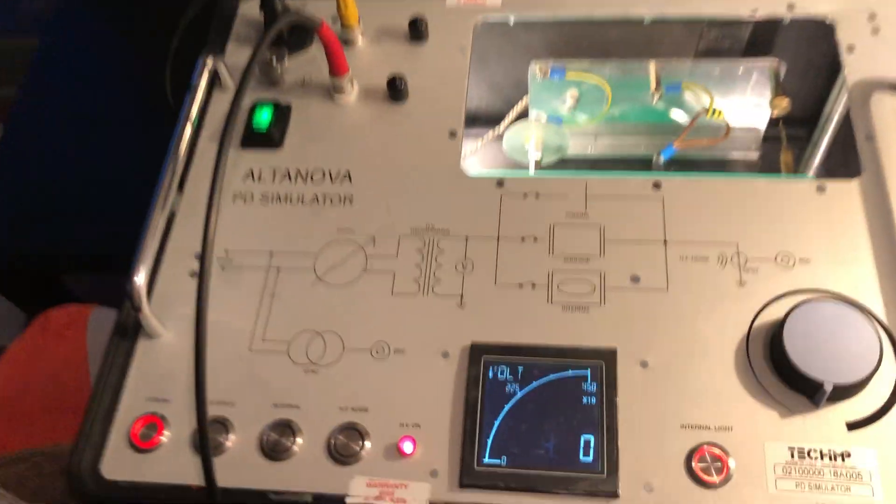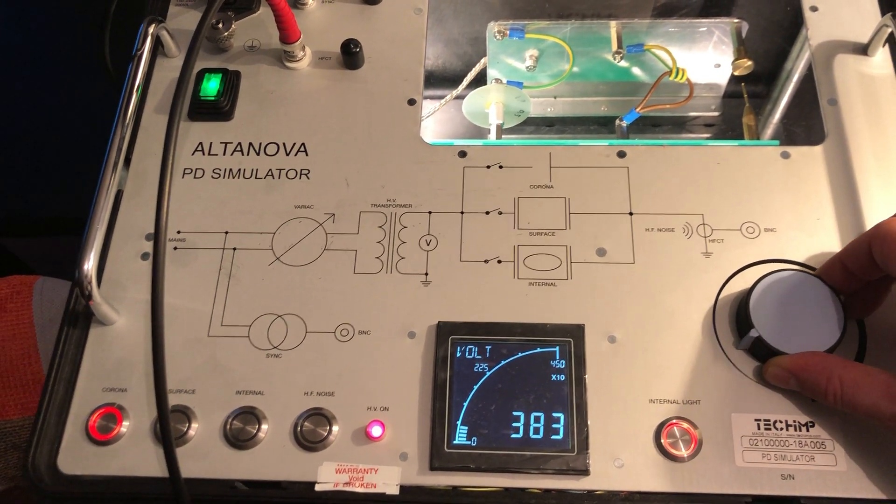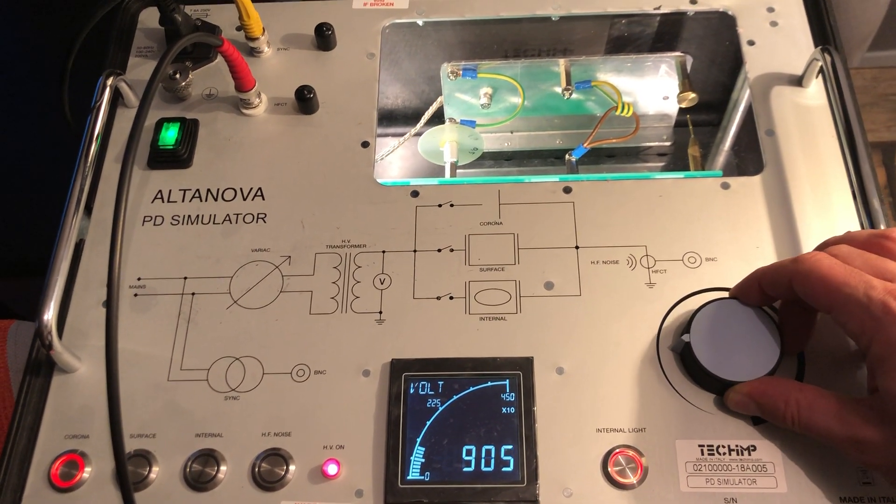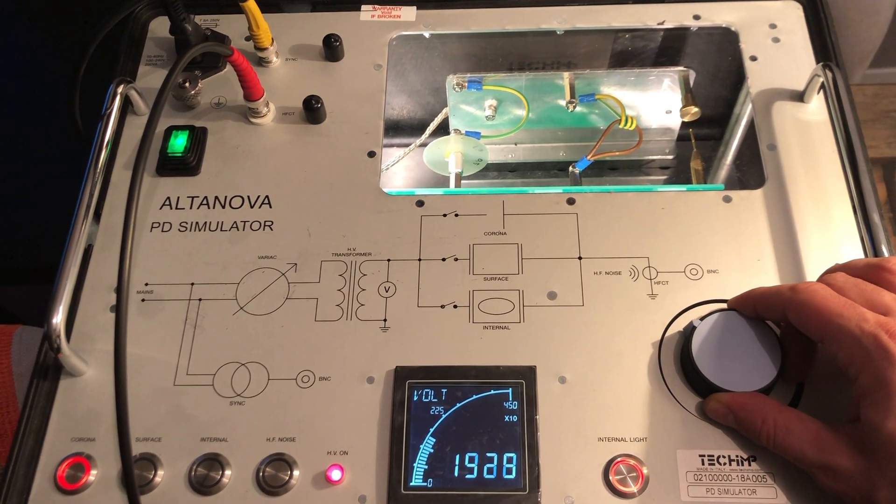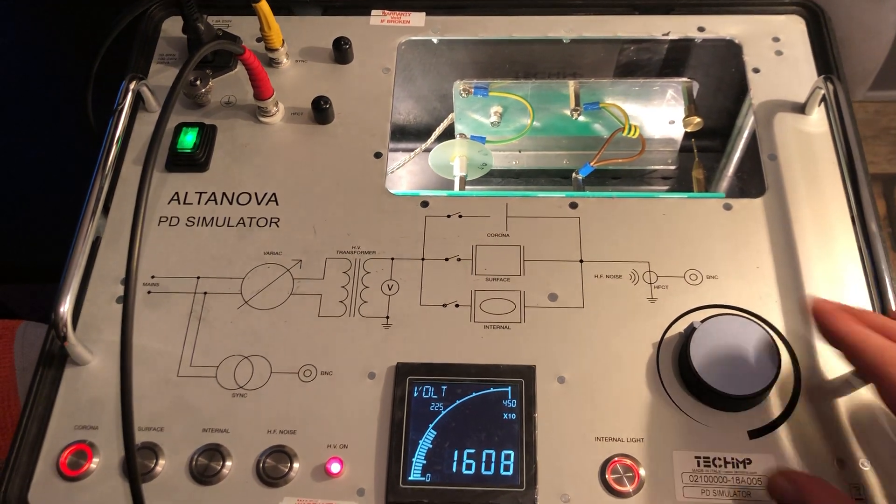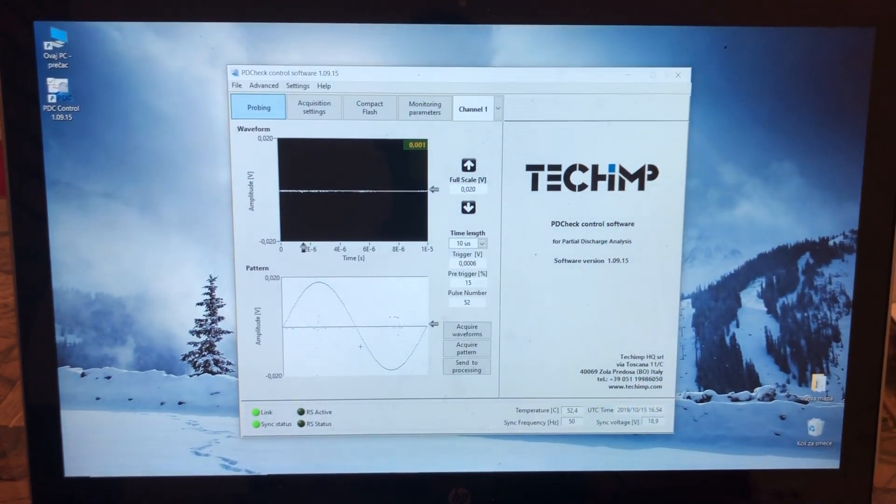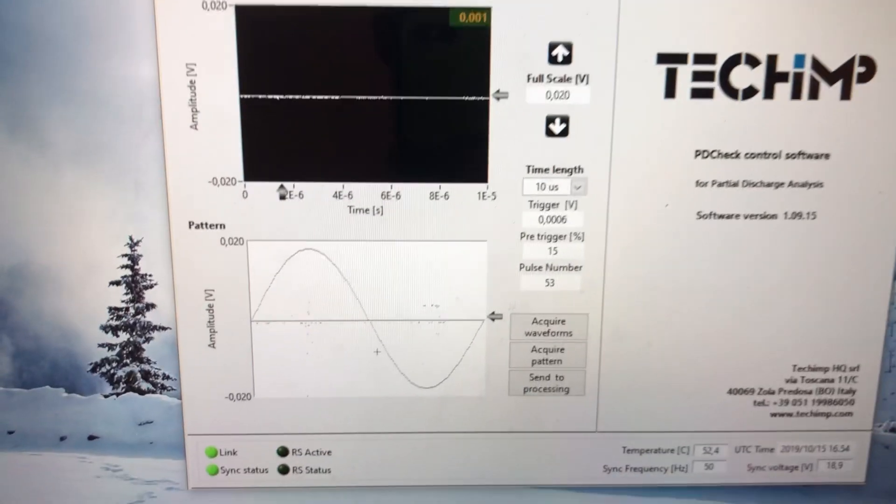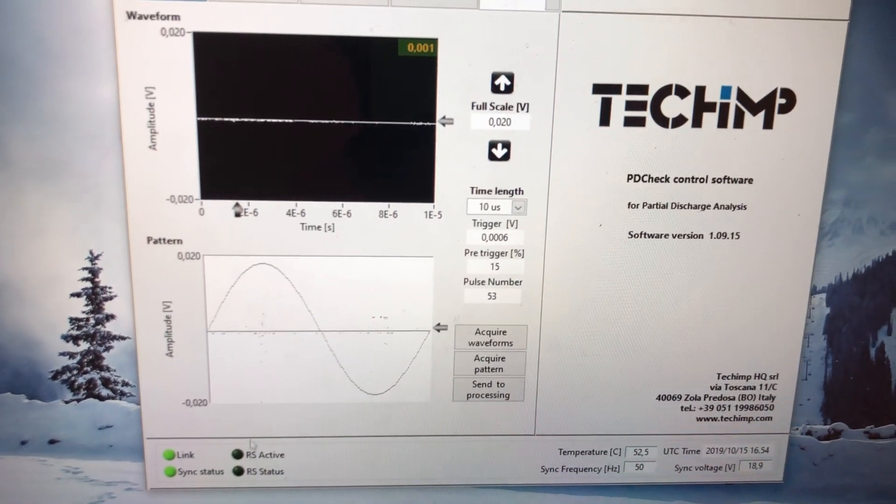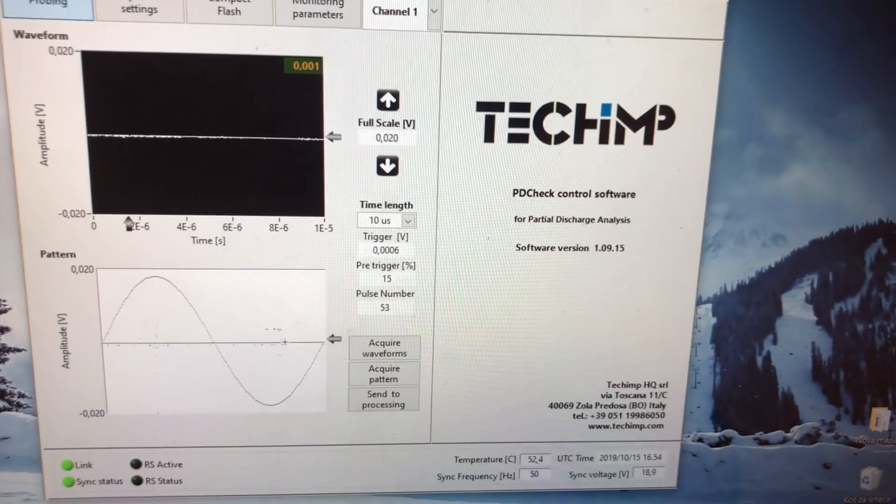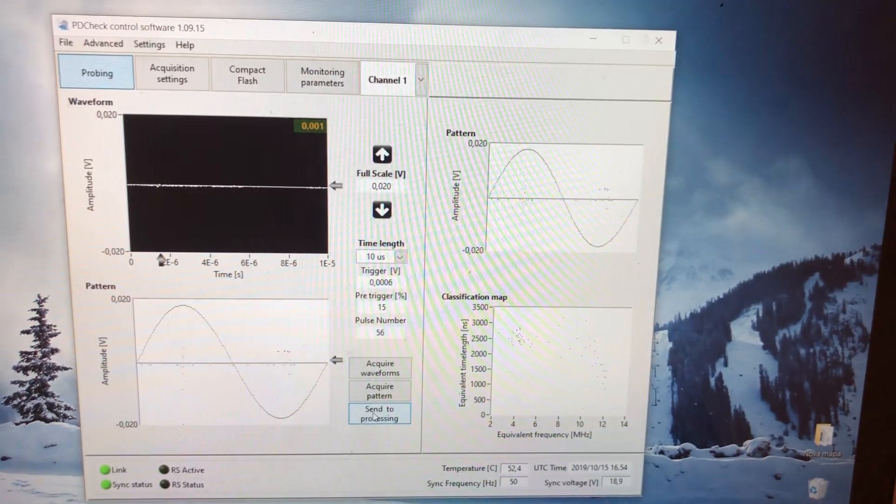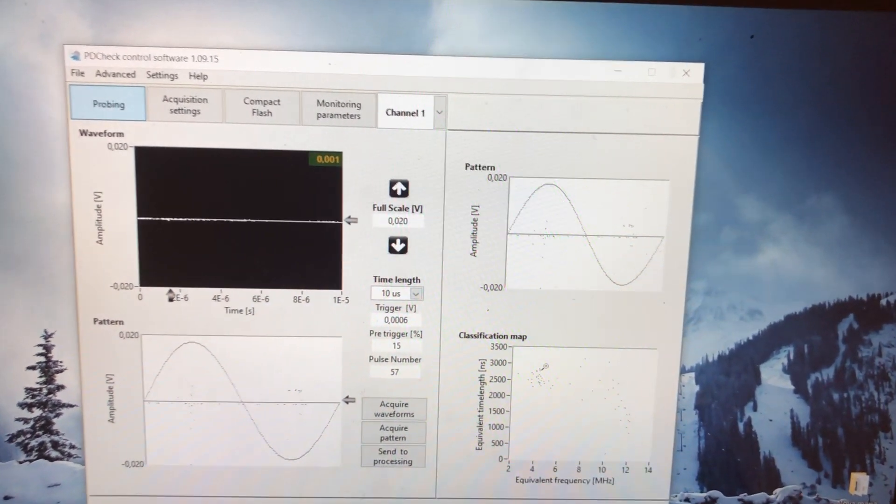I expect the signal of Corona to come at around 1800 volts. So let me first increase this to a value below that, let's say 1600, and this would be more or less it. Now let's see if we have something here. The only thing I see here right now is noise. If we take a closer look, we will see that there are some dots here, but these dots do not represent Corona. We will see that later. Regardless, I'm going to send to processing and here I have some points.